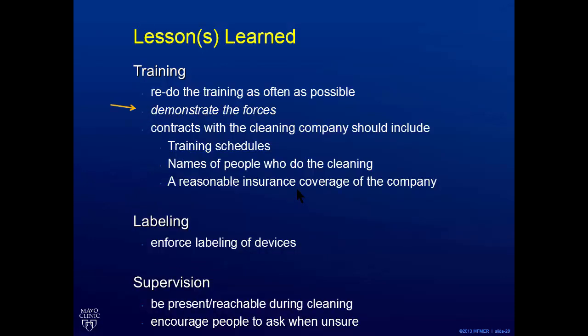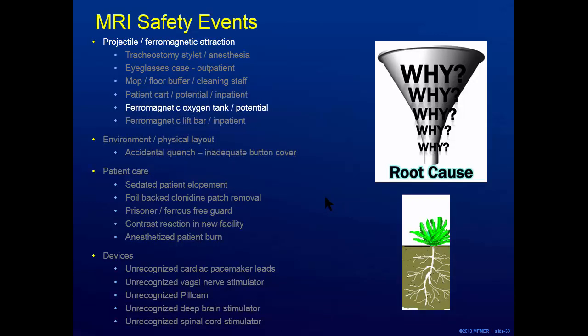The lessons learned from this are that it's so important to demonstrate to people who have reason to be in that area the actual forces involved. We do this a lot with our people using a steel wool ball wrapped in duct tape — it doesn't have much ferromagnetic mass, but just getting that sense of pull and letting people play with it in the magnet room makes a great impression. And obviously, supervision is essential in these situations.